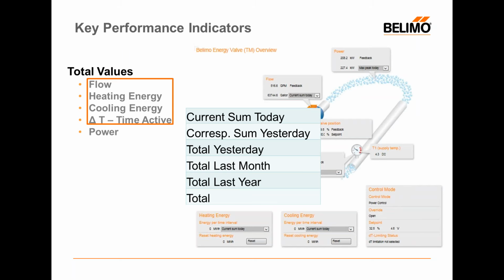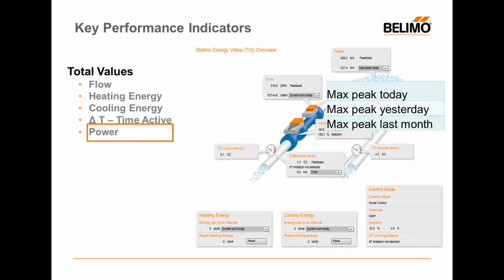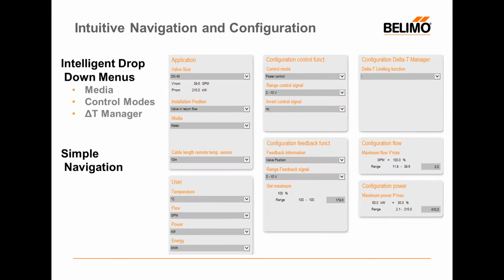For the flow, heating, and cooling and active Delta T Manager, we'll do current sum of today, corresponding sum of yesterday, totalization for yesterday, last month, and last year, and total time that the valve has been operational. For power totalization, we'll give you a maximum peak of today, yesterday, and last month.